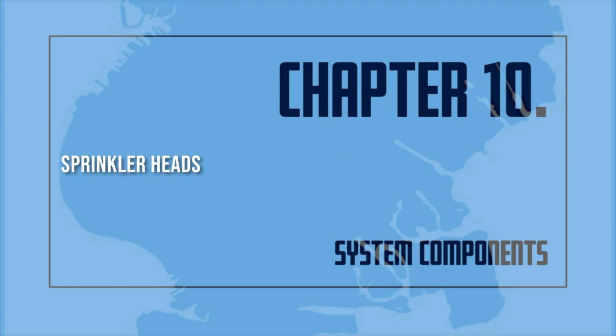In places where the temperature is normally high, such as boilers, ovens, and drying rooms, a sprinkler head with a higher temperature rating must be used. This is to make sure that the sprinkler head does not discharge water at the wrong time. If heads with a high temperature rating are used in an ordinary room, like an office, an apartment, and store, the value of the sprinkler protection is greatly reduced. This is because the temperature will have to increase much higher for the sprinkler heads to open.